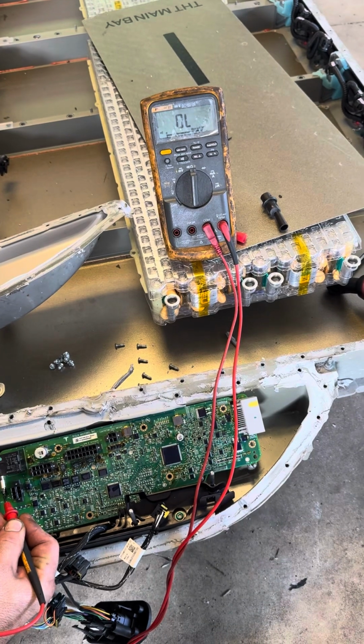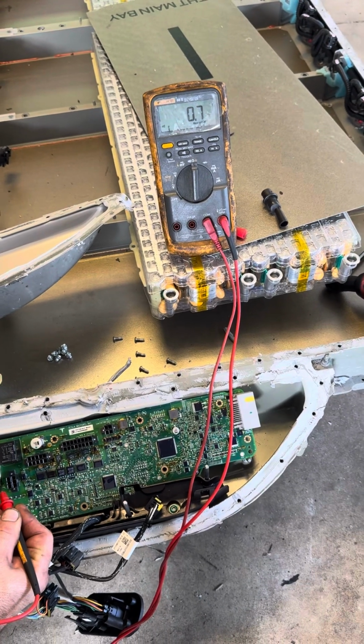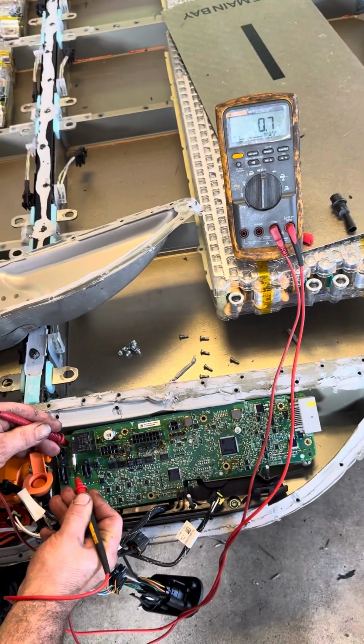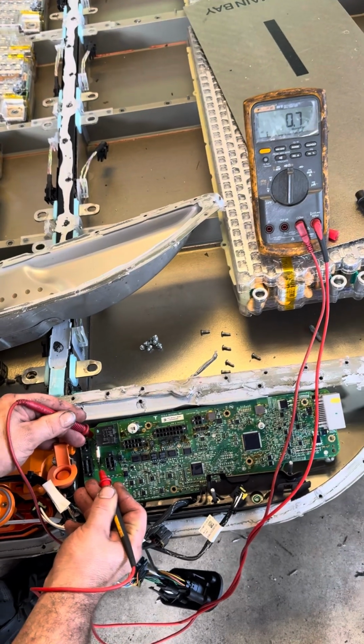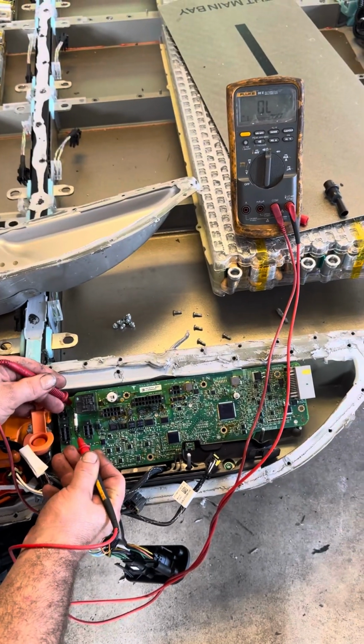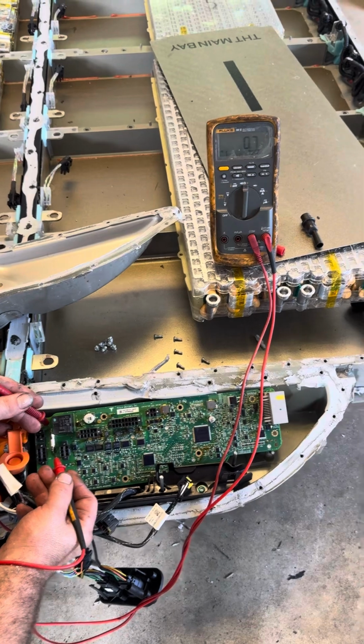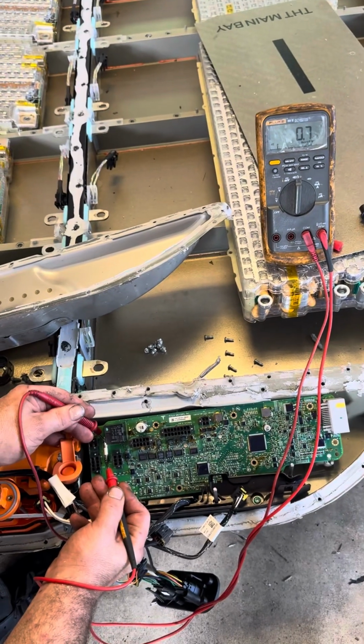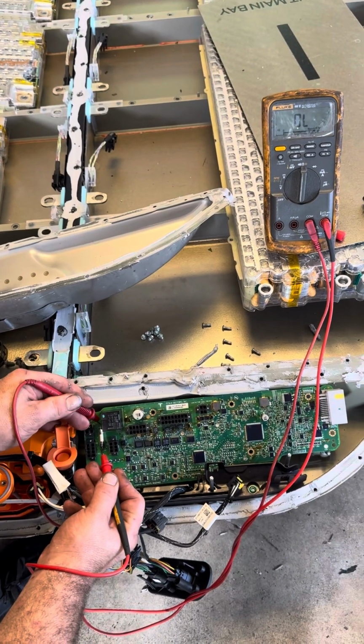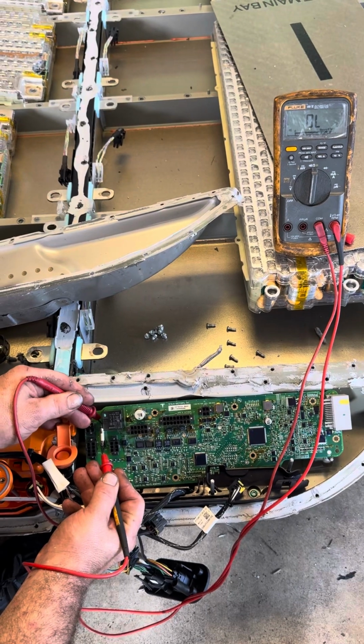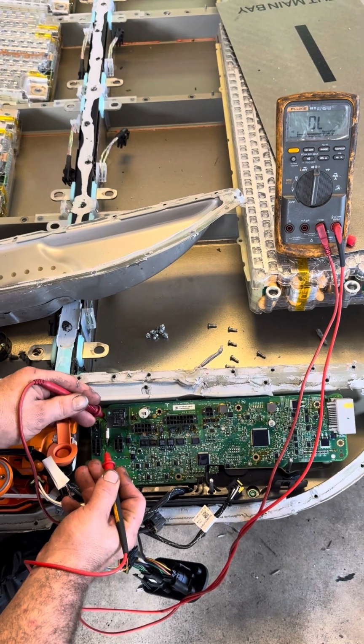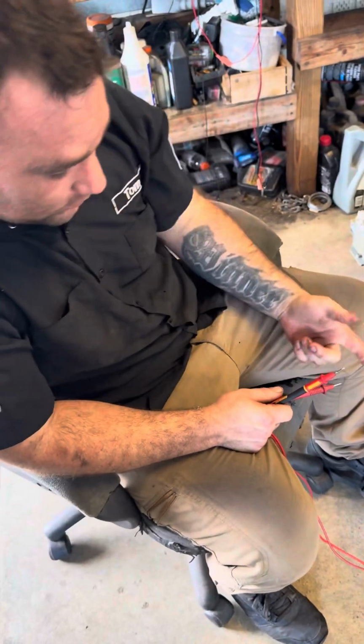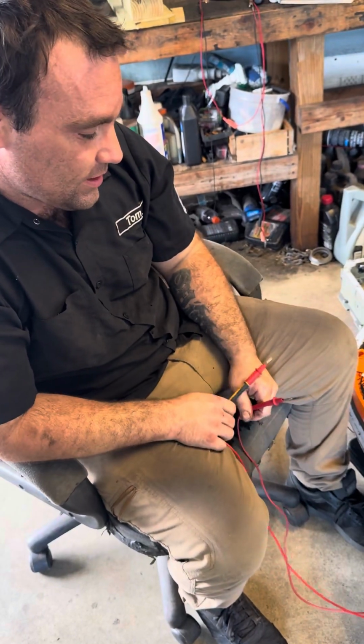So it's like it's got high resistance, 0.7. You're only allowed 0.2, 0.3 in a system, and this has 0.7, and it's intermittent. Yeah, see, there it goes. Intermittently stopped working. And I know this meter's good, it's a Fluke. So I also think we should replace the BMS board on this. So we'll get you an estimate here shortly.